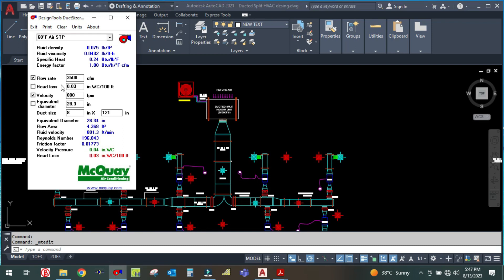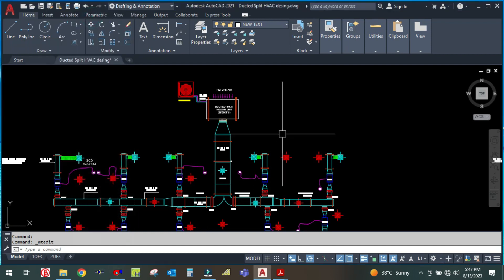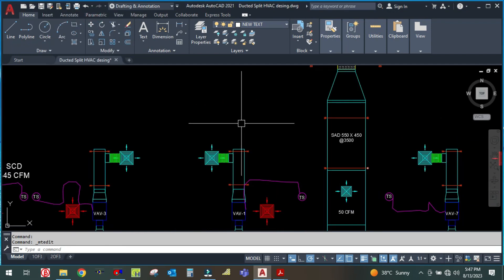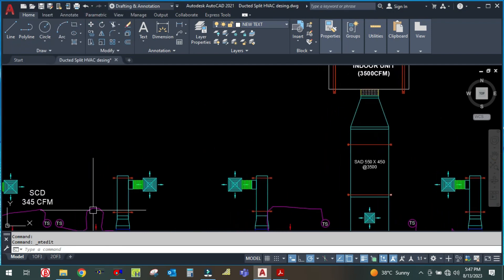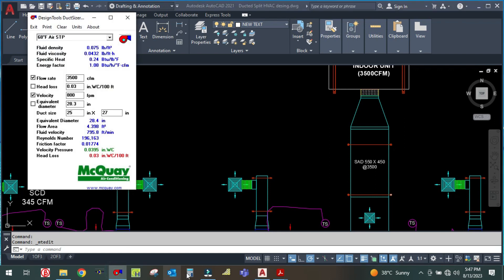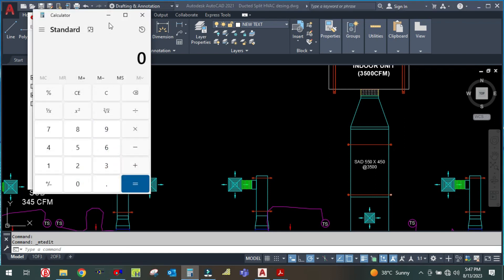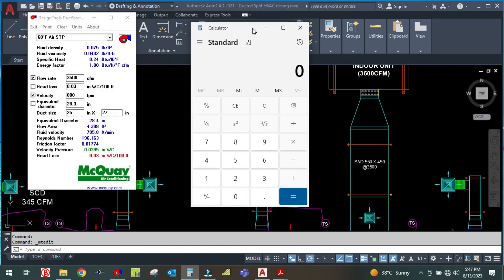The CFM is 3500 and the velocity is 800 feet per minute. Enter those values and then enter the height. Let us assume the height — let me check: 26 inches.